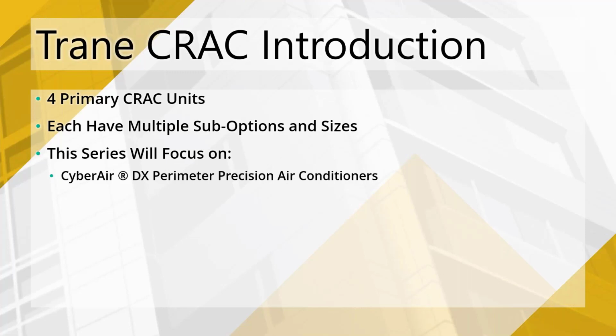Now, specifically within this, we are going to be building the upflow configuration. We could also build the downflow. It's just an additional set of options, probably an additional type catalog. I'd probably save it as a new family just to keep my end user's navigation of this as easy as possible. So I'm going to build one of these variants, which is the upflow. And I'm going to be focusing in today's session on the 88 kilowatt version of this, and we'll build out the other types and sizes in part 2, just so you have an idea of where we're focusing here.